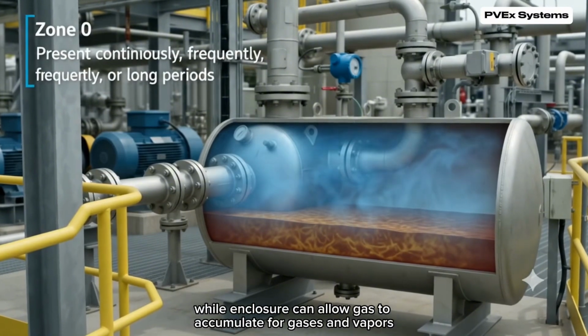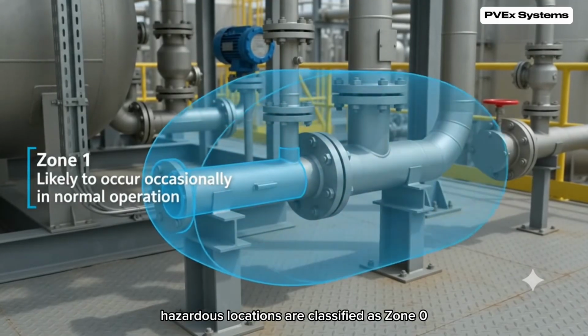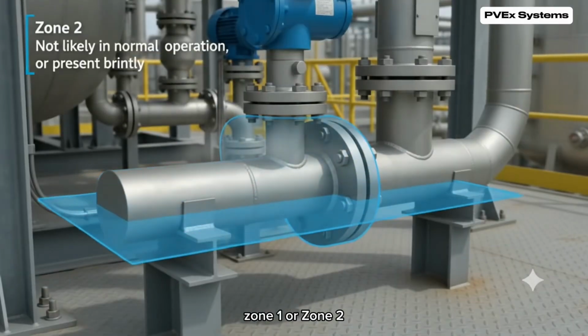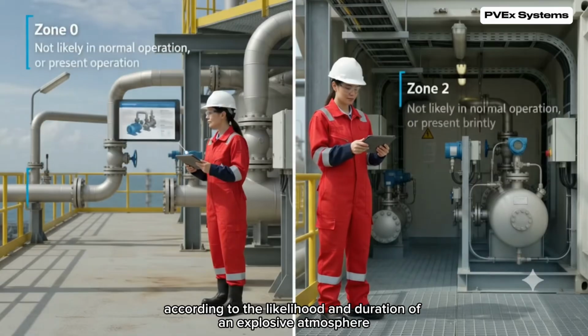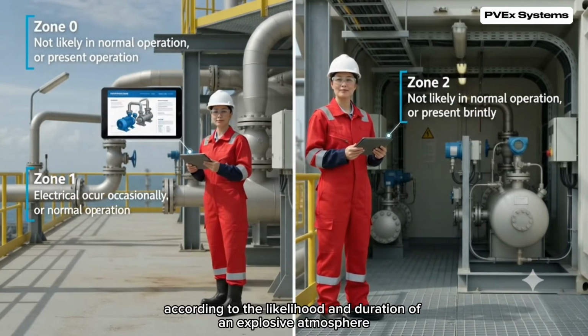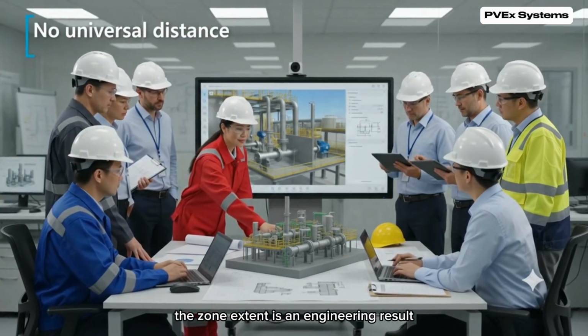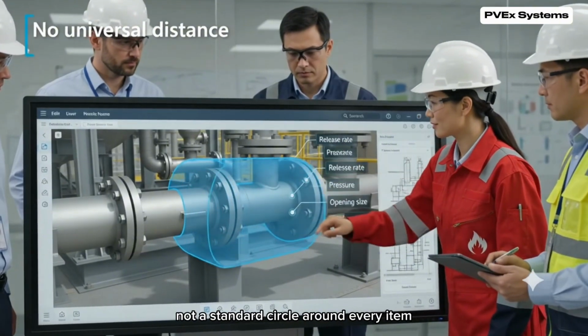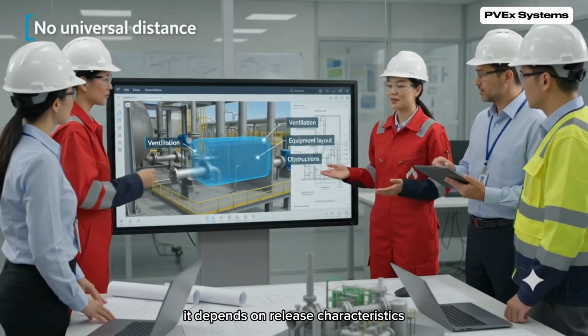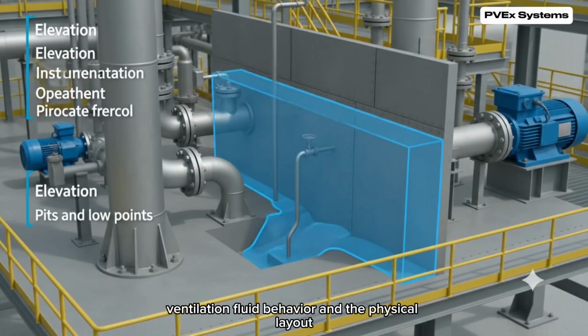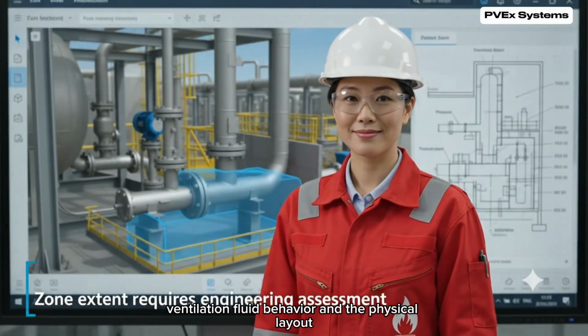For gases and vapors, hazardous locations are classified as Zone 0, Zone 1, or Zone 2 according to the likelihood and duration of an explosive atmosphere. The zone extent is an engineering result, not a standard circle around every item. It depends on release characteristics, ventilation, fluid behavior, and the physical layout.